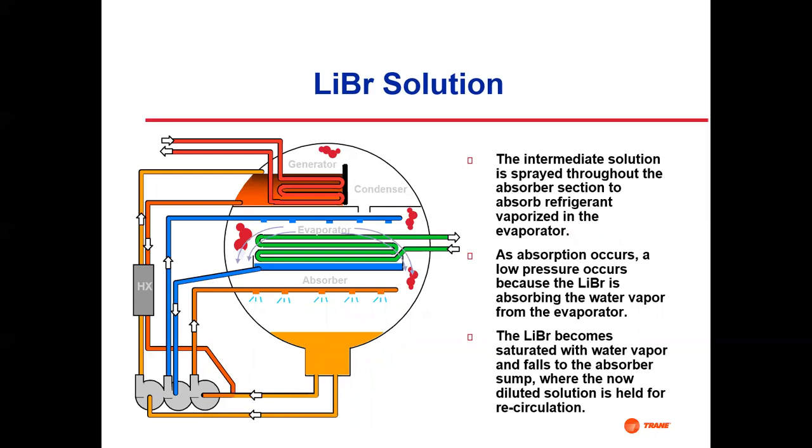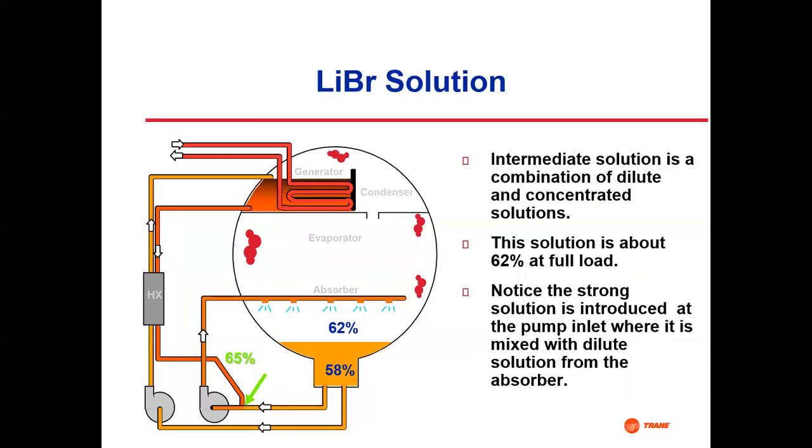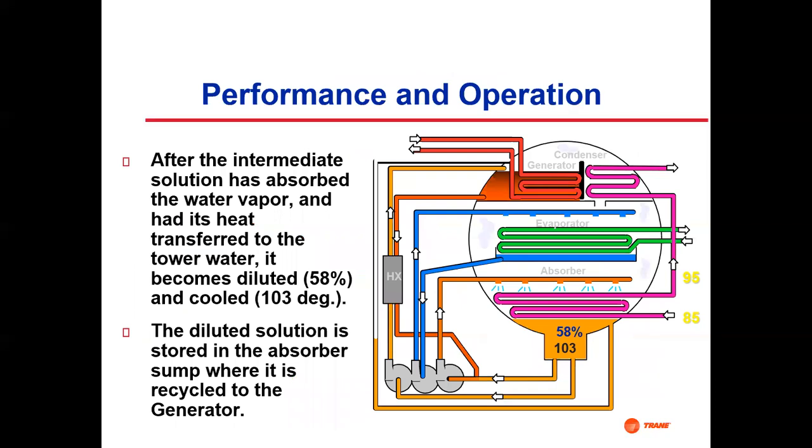I think we've talked through all that. And of course, the other thing to keep in mind is that this is exothermic. So actually, in the absorber down here, when this stuff is getting absorbed, it's giving off heat. And that's why, when we get the whole cycle up here, this cooling water comes in, to suck up that heat. This thing would just overheat if you didn't keep it cooled down, because it's giving off heat there. And then, of course, we have to have cooling up here to condense the water vapor that's coming across from the generator.